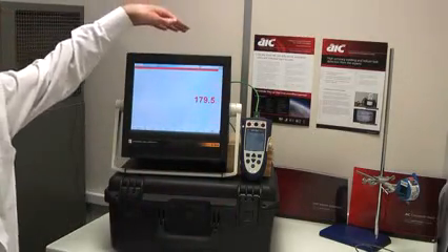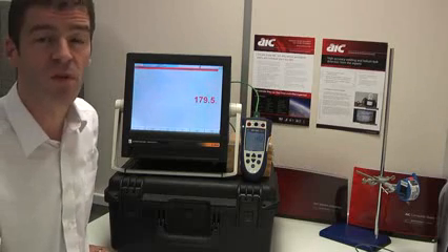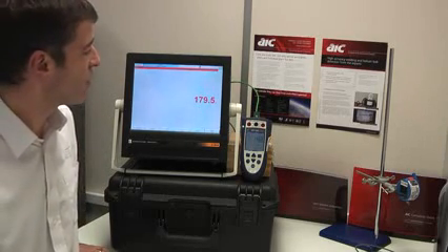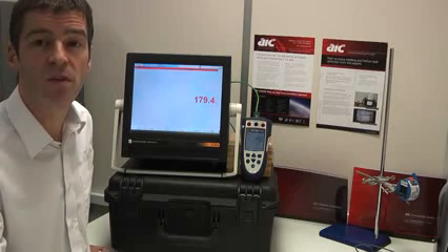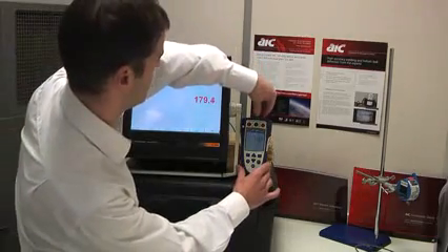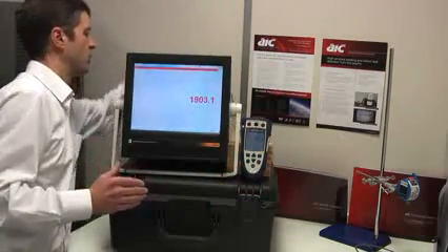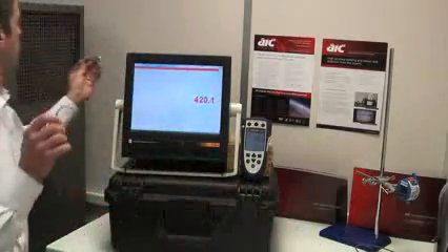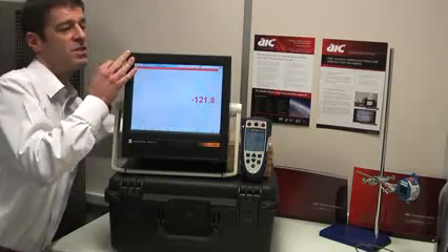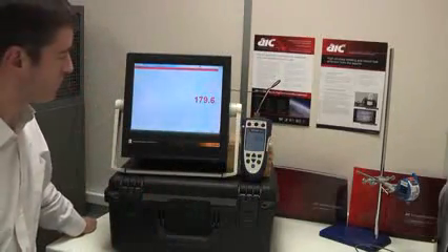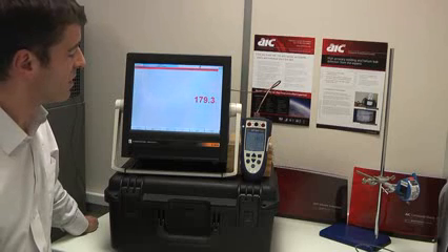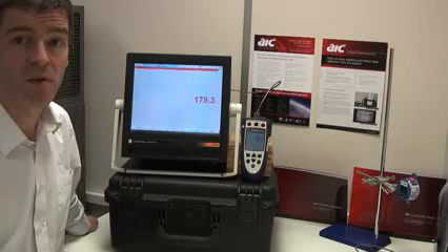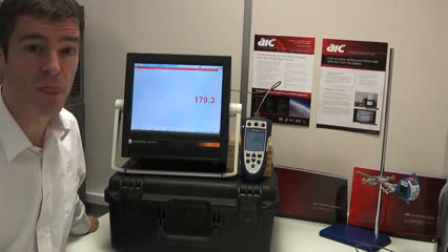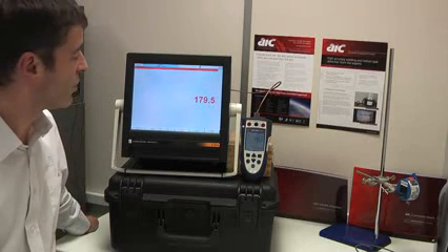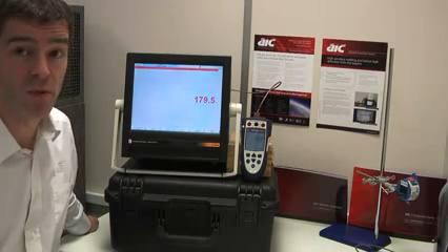In this case, the cable is just passing through around the back of the instrument here, and so there's very little temperature gradient along the back, so there's almost no scope for the incorrect cable to have an impact. Just change it again for Type T. The voltage generated by Type T at 180 degrees C ought to be equivalent to about 280 degrees in Type N. And again you see negligible difference. Well, I'll put some heat into it, I've been handling it, but again 179.5, half a degree's difference, not the 100 degrees difference you would expect. And given a bit more time to stabilise, that comes back to about the right point.